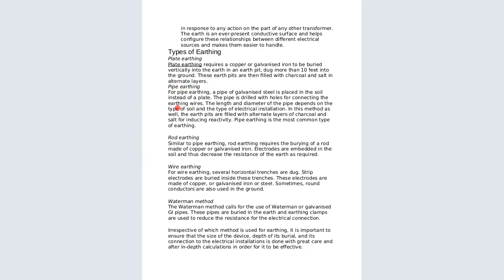So pipe earthing. What is pipe earthing? For pipe earthing, a pipe of galvanized steel is placed in the soil instead of the plate. The pipe is drilled with holes for connecting the earthing wires. The length and the diameter of the pipe depend on the type of soil and the type of electrical installation. In this method, as well, the earth pits are filled with alternate layers of charcoal and salt for inducing reactivity. Pipe earthing is the most common type of earthing, the one that is locally used.